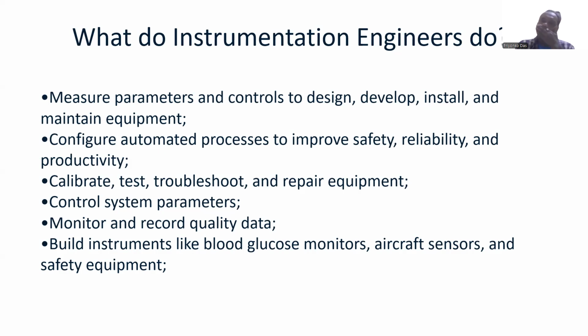Not only developing that process, but your instrument or sensor should have reliability. Unless the sensor is reliable, you cannot use it. Suppose you are measuring temperature and your sensor gives a reading of 1025 degrees Celsius, but the actual temperature is 1050 degrees Celsius. Since your measured data has an error of 25 degrees Celsius, that data is not reliable, and obviously this affects productivity.